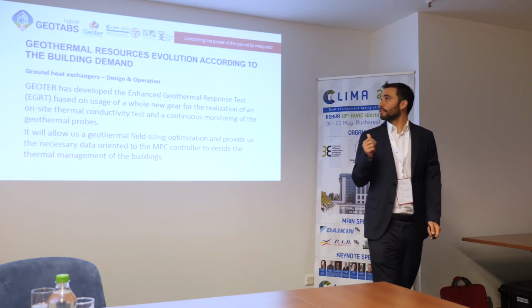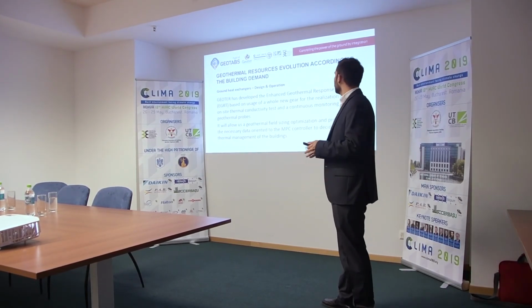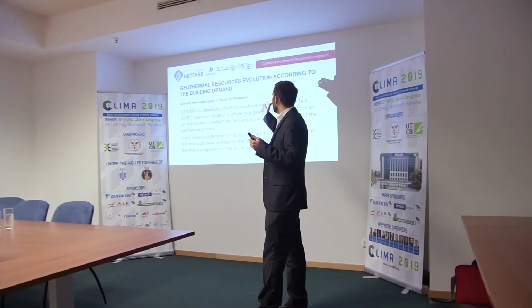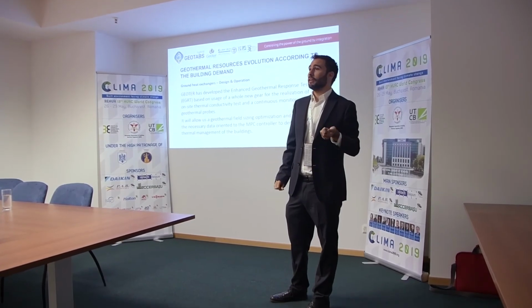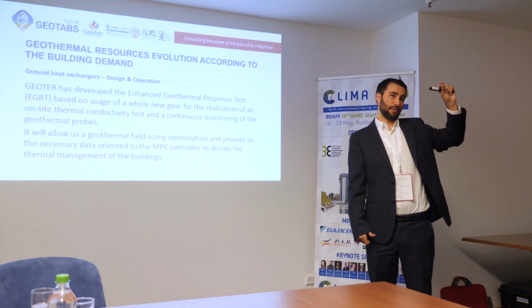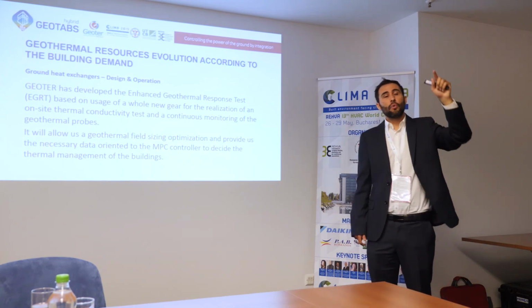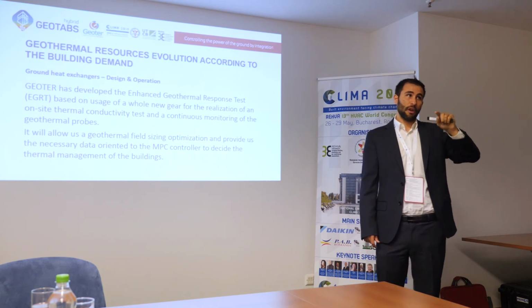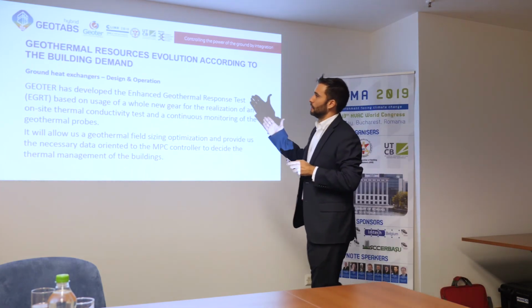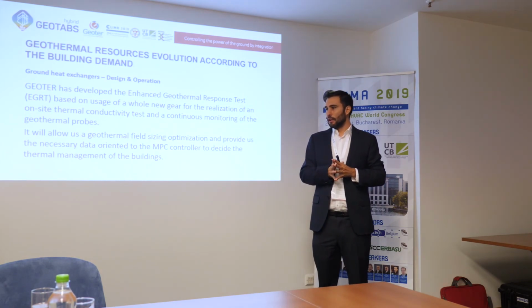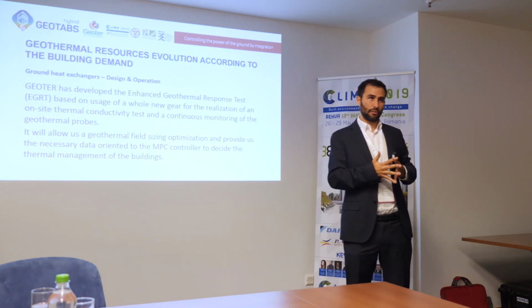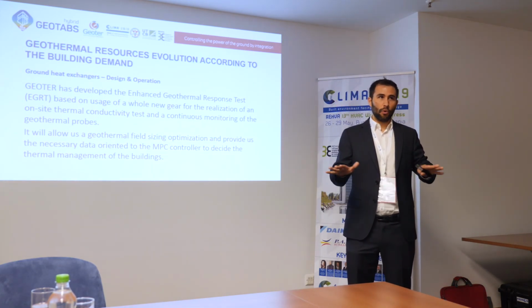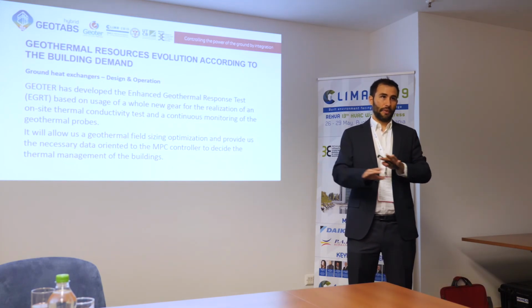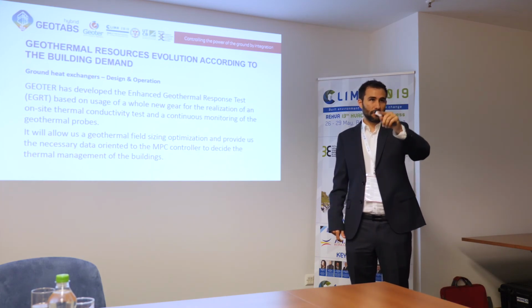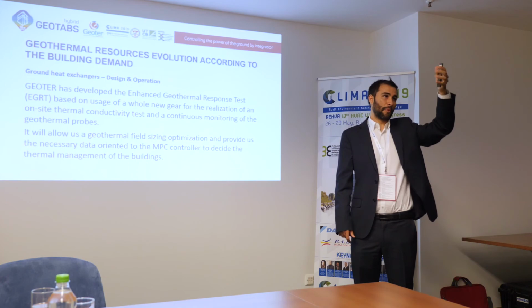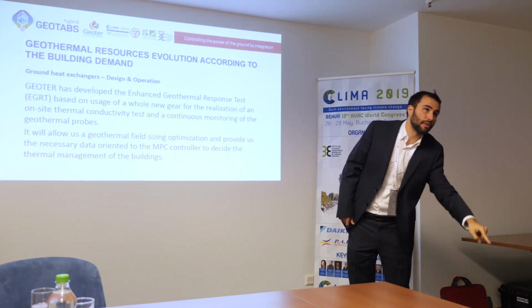So, in this project, GEOTER has developed an improved system, the enhanced geothermal response test. In this case, we introduce little sensors inside of the geothermal probe in order to know the thermal conductivity at all the levels of the borehole. The test is somewhat different, because we don't circulate the water inside of the probe. In a first stage, we leave the water for 24 hours in the geothermal probe without movement, and we lower a little sensor which takes temperature and pressure data along the whole borehole, 120 meters depth.